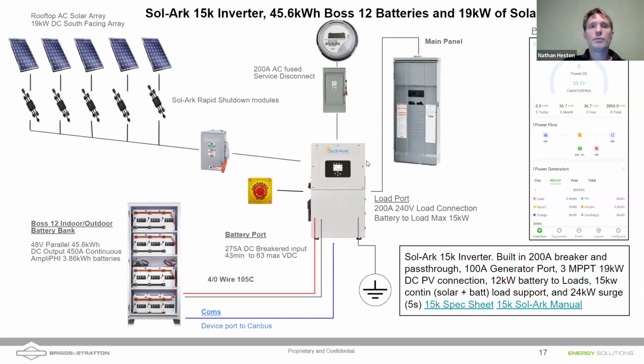The Sol-Ark 15k is much better suited for whole home backup. What we're looking at here, we can have 19 kilowatts of DC coupled solar coming into the Sol-Ark 15k. Notice the big difference here: coming from the grid, I'm running a 200 amp fused disconnect straight into the Sol-Ark inverter. No loads prior to the inverter. All the loads are coming after the inverter here. And so the inverter is capable of supplying that 200 amps, passing that 200 amps through to the loads.